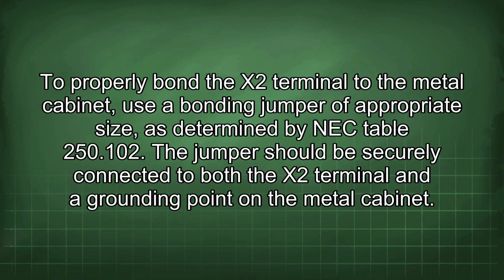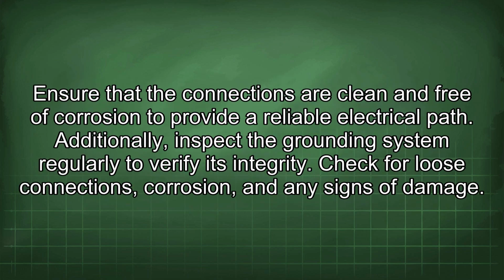To properly bond the X2 terminal to the metal cabinet, use a bonding jumper of appropriate size as determined by NEC Table 250.102. The jumper should be securely connected to both the X2 terminal and the grounding point on the metal cabinet. Ensure that the connections are clean and free of corrosion to provide a reliable electrical path. Additionally, inspect the grounding system regularly to verify its integrity. Check for loose connections, corrosion, and any signs of damage.